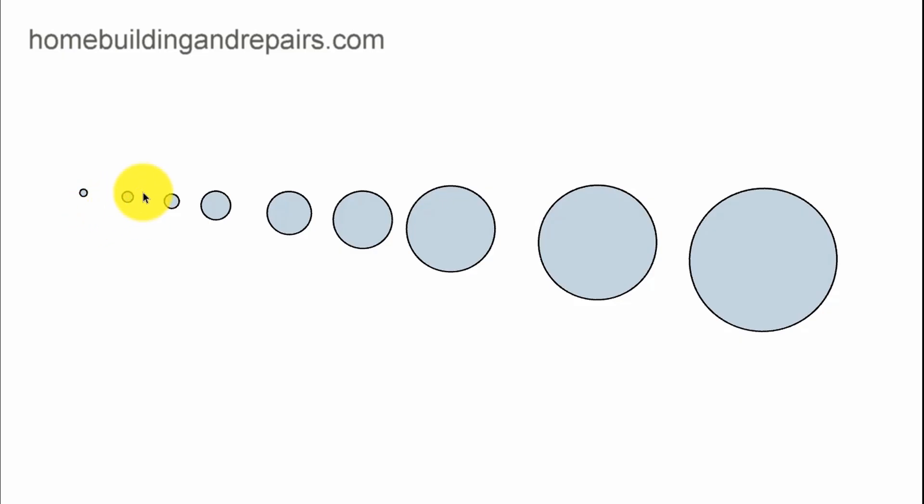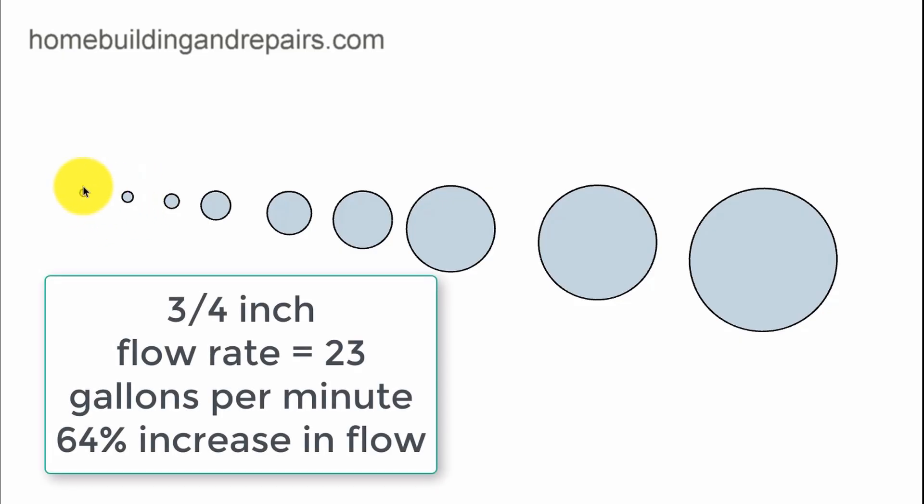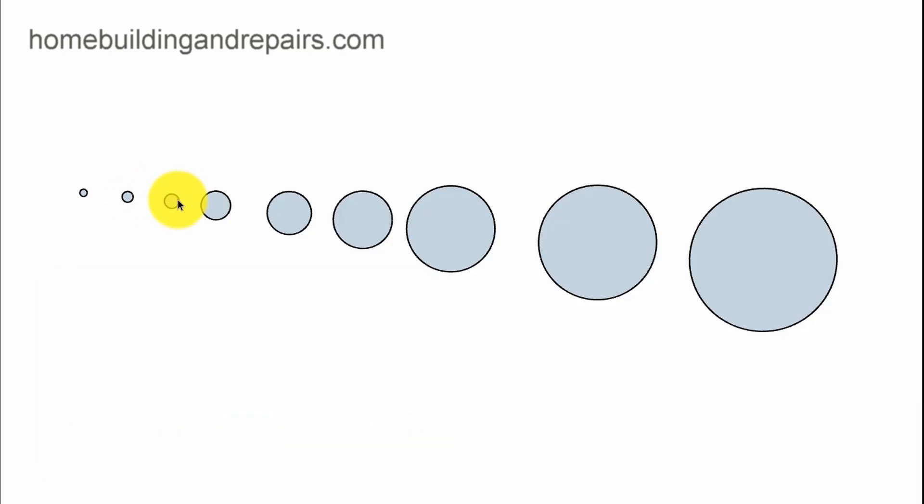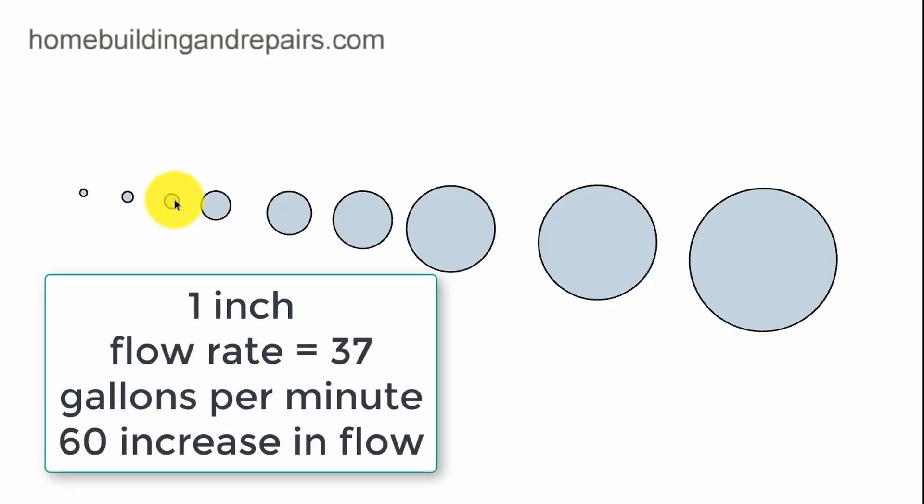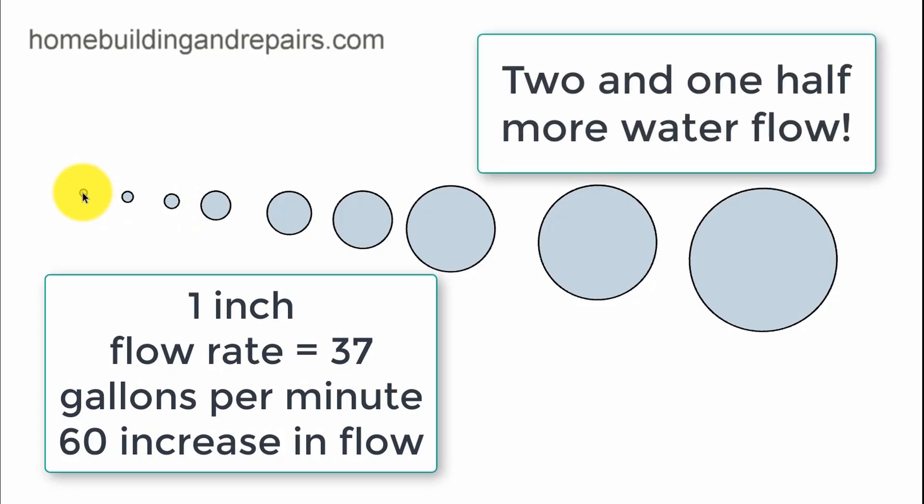Those are going to be in gallons per minute. A 1/2-inch pipe can fill up 14 gallons in a minute. That's how much water can run through this pipe at a specific PSI. A 3/4-inch pipe is 23 gallons. If you think about it, 28 gallons would be double, and we're only raising the diameter of the pipe by a quarter of an inch. When we go to a 1-inch pipe, we are now getting 37 gallons per minute, more than double the 1/2-inch pipe.